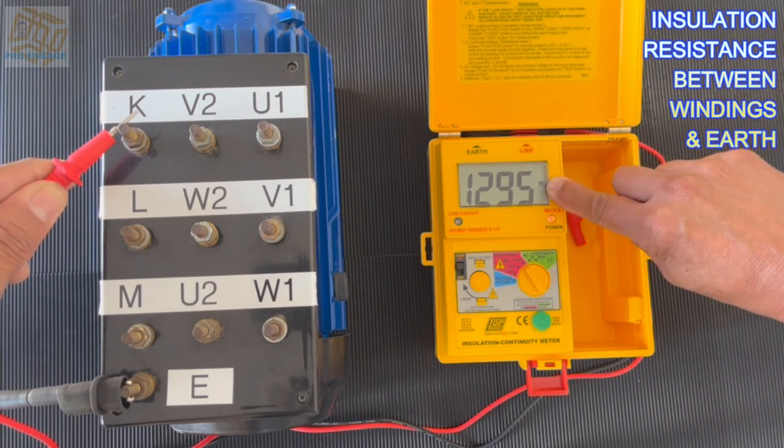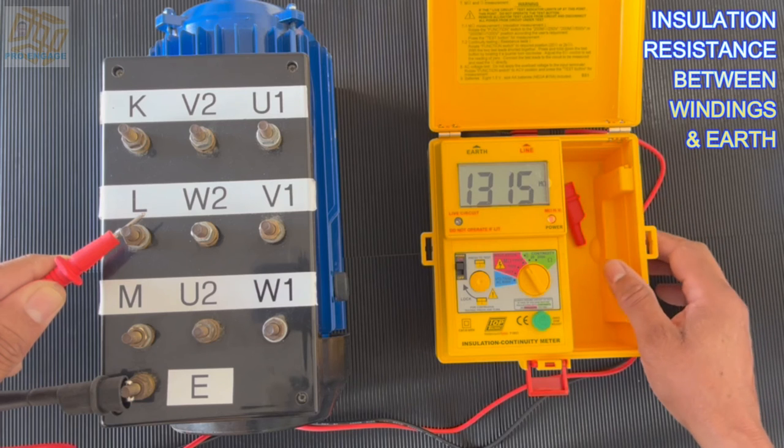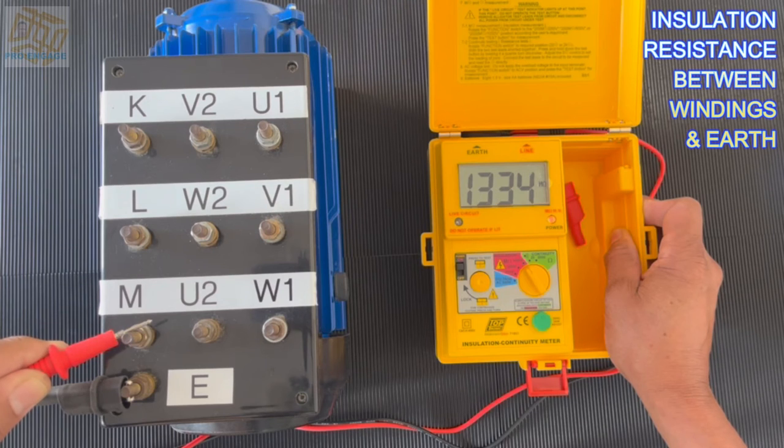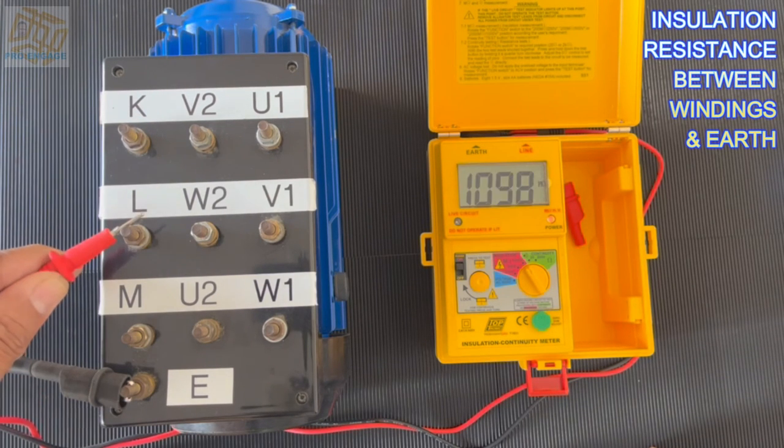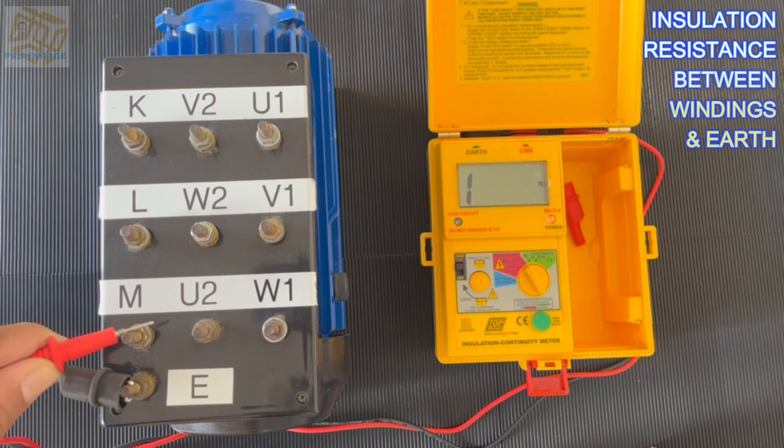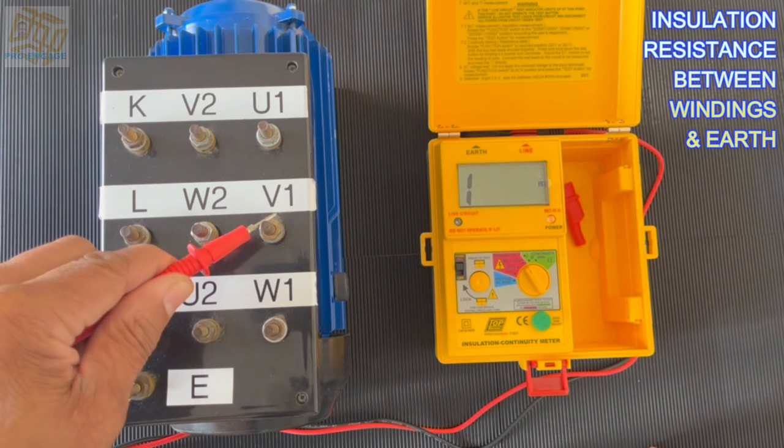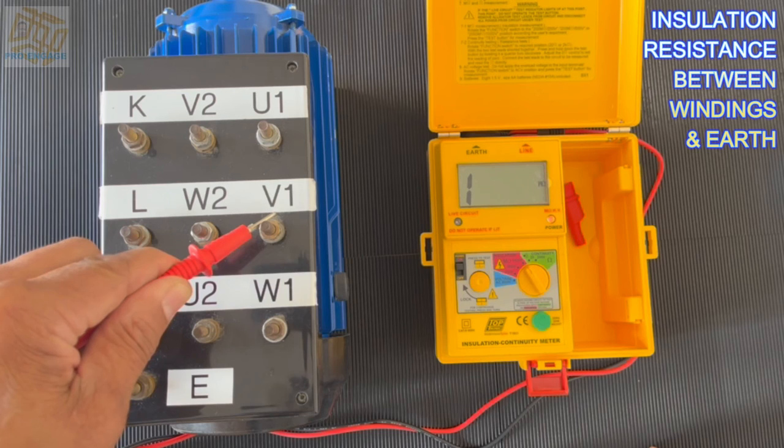Interestingly I find over a thousand mega ohms. So with regards to the analog scale this would deflect all the way to the left. Same here, 1300 probably, slightly more if I keep it longer, moving towards infinity. Remember on the analog scale there is no 1300. It moves to 200, 100, 200, 500, 800, and then it's infinity. So this reading is somewhere between 800 and infinity. You might as well just write infinity.